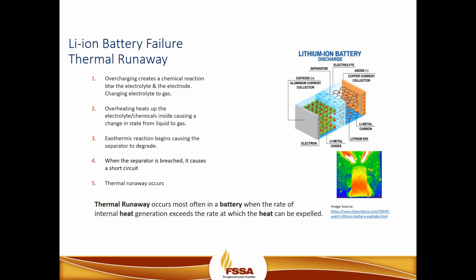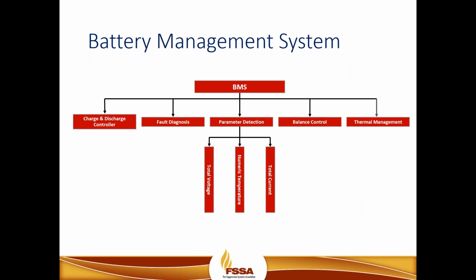Now, if we look at the overheating process, it is very much like boiling water, if you will. Just like when you boil water, it changes state from a liquid to a gas. The same is true with the electrolytes inside of the battery. As they're overheated, whether it be from an abuse factor or whether it be from an external factor, maybe a fire event external to the battery, those liquids will begin to boil and change state from a liquid to a gas. And if you're using a cylindrical type battery, they'll be vented into the space.